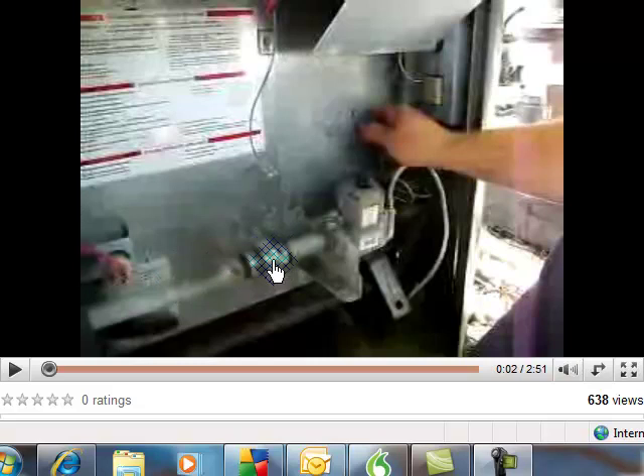This is a gas line. Here is a gas union. They can be taken apart and pulled out. The reason why you don't put a gas union inside of a cabinet — why it's against the law — is because it is capable of loosening up, purging out gas, and when this heater is ready to fire up, it'll be an atom bomb.